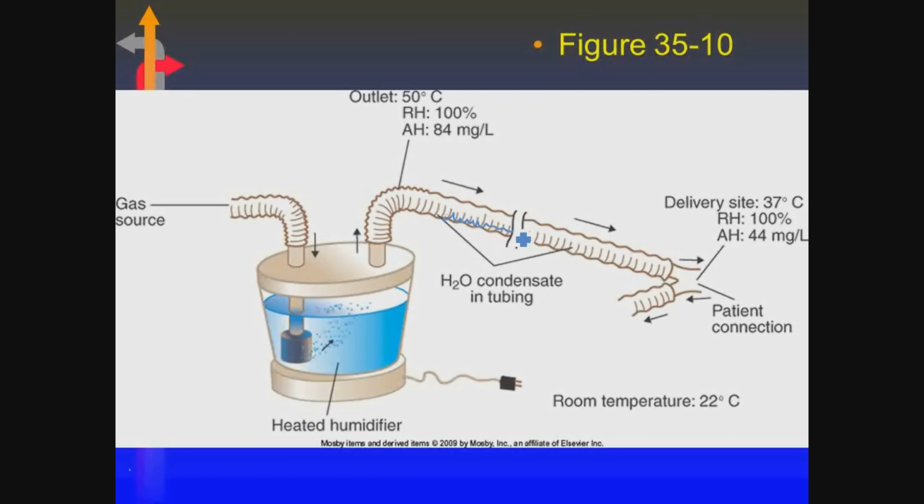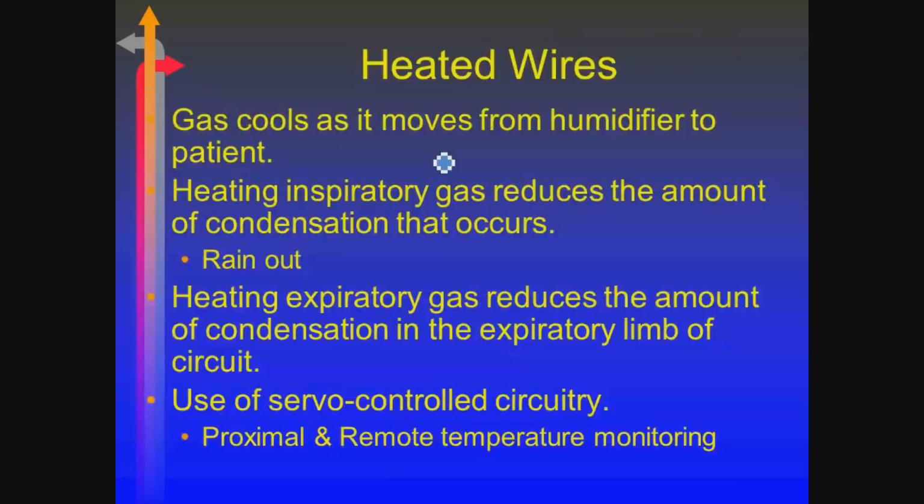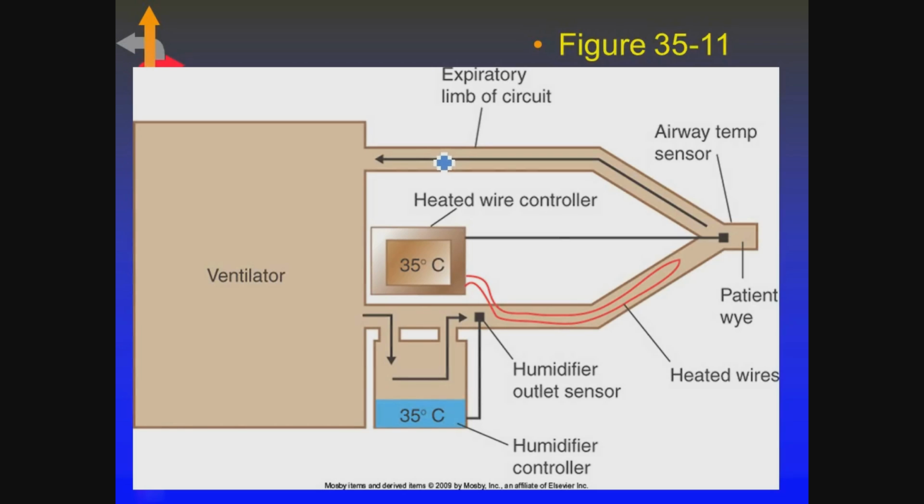All this water collects in the circuitry. If I then lift this portion higher than the patient, it runs into the patient. I have now lavaged them with condensate. Not a good idea. So you've got to be careful if you're using that. And that's why we use some heated wires to prevent that rain out, that condensate from happening. I'm going to let Mary talk about that in the fall. And you can see the wires inside the circuitry.